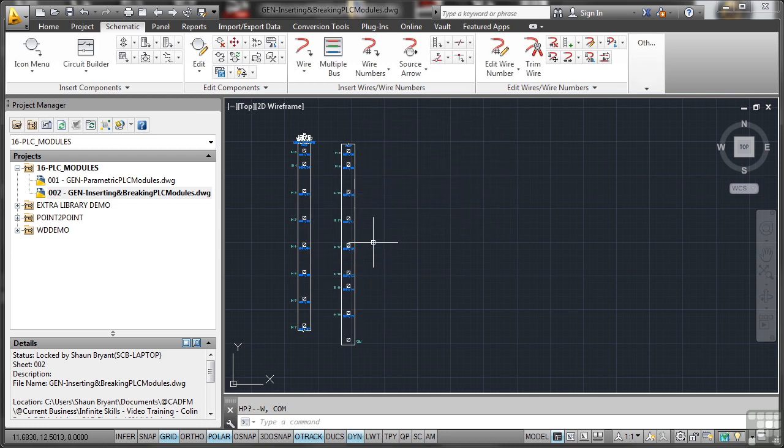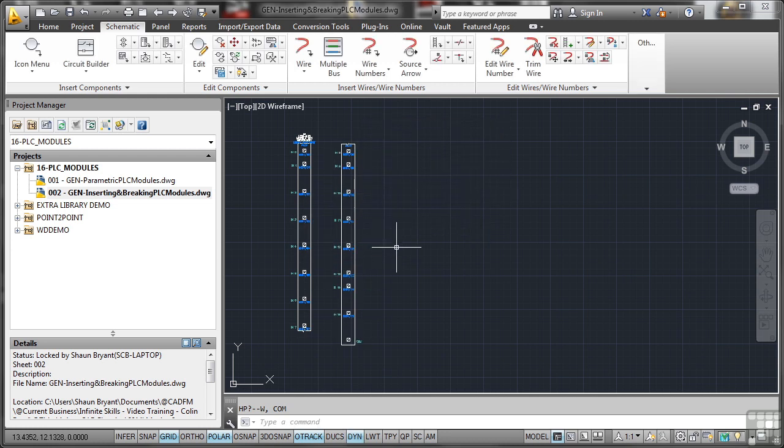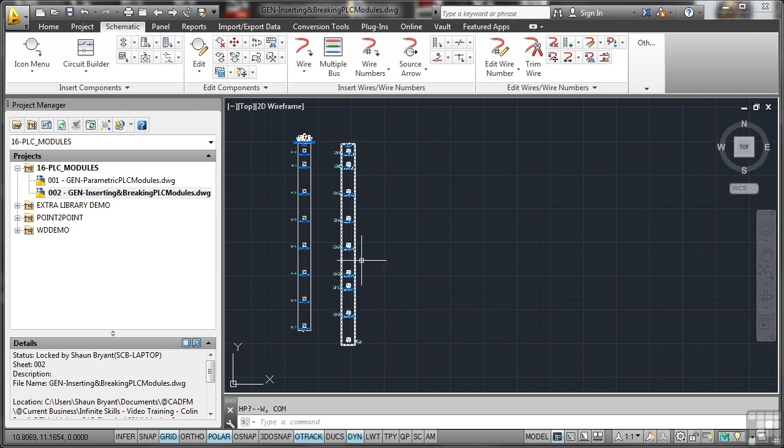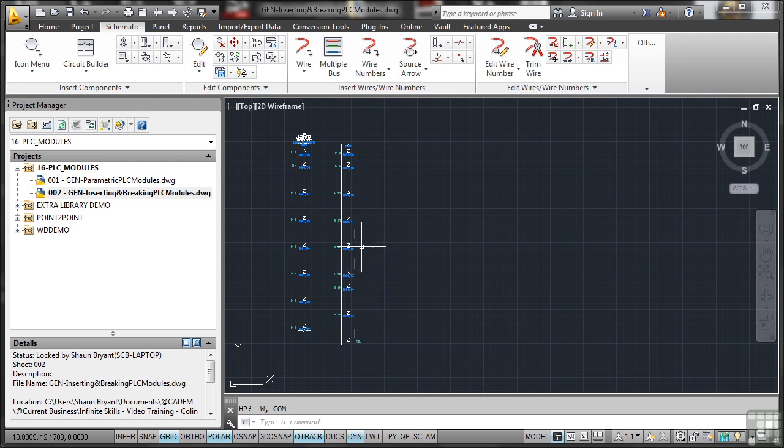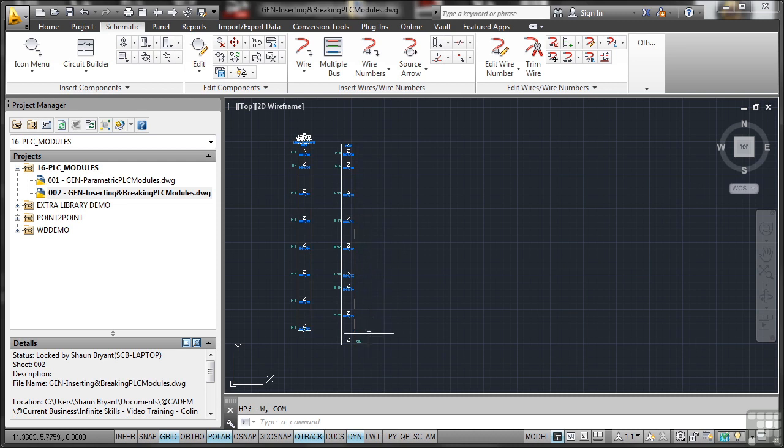I'll just do decimal for now. Did you notice that it was going off the end of the PLC module? And what was amusing was it looked like it was actually going to go off the end and just into space there. The good thing about AutoCAD Electrical, because this is parametric, it'll actually set it up for you. So it actually sets up the length. You're literally creating a custom PLC module using that insert and break tool. So try and use parametric PLC modules wherever you can, because you can customise them to fit into your AutoCAD electrical drawing.